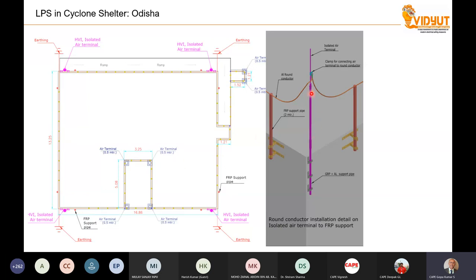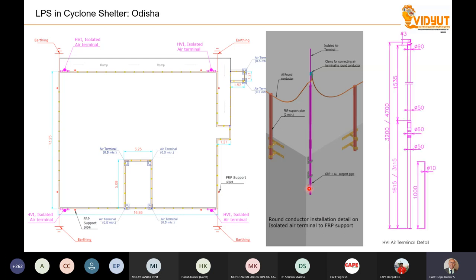So now what is done here? Somebody made a beautiful proposal. There is an insulated pole. The air termination mesh is running on the insulated pole. The down conductors are HVI isolated air termination. HVI means some kind of a special down conductor. And this particular down conductor, for example, is a copper wire, 35 millimeter square high voltage cable. The cost of this cable is about 3,500 rupees per meter. So this kind of a lightning protection system is proposed in the state of Orissa, and I think several hundreds of cyclone shelters are protected with these kind of things.